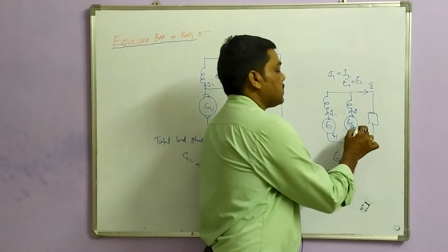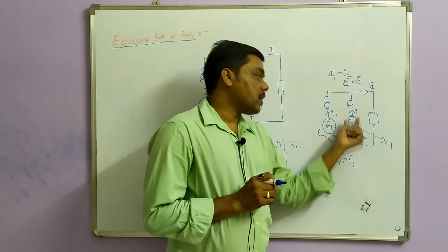Now at one condition, what happens? The total load is borne by generator 1, and generator 2 acts as a motor. See what happens to generator 2 as the load on generator 2 decreases. Now it acts as a motor, and the other acts as a generator, and this generator is fully loaded. There is no load on generator 2, it is becoming a motor. That means it is going to take current, and the total load is supplied by generator 1. Now these are the consequences. So one DC machine acts as a generator and another machine acts as a motor. That will be compensated by connecting an equalizer bar.